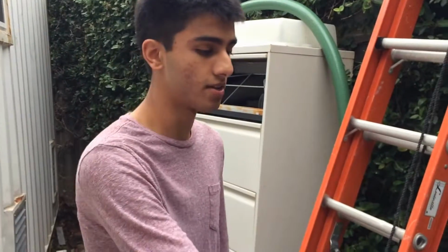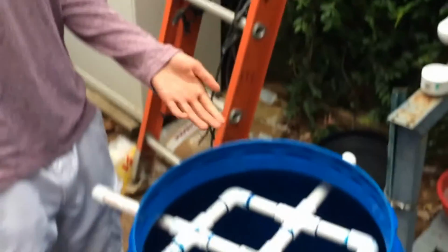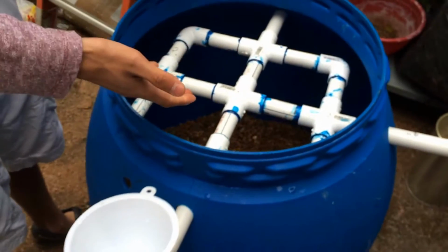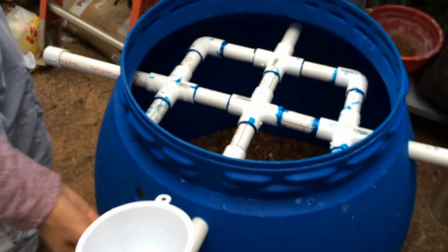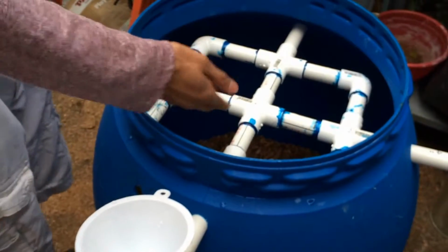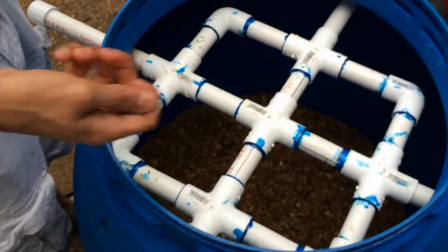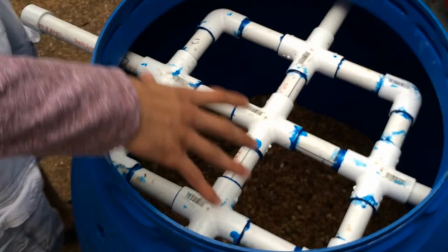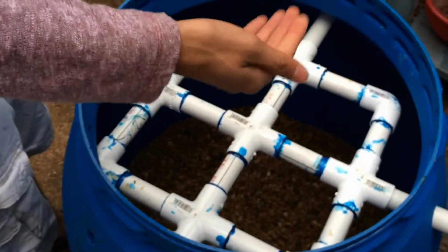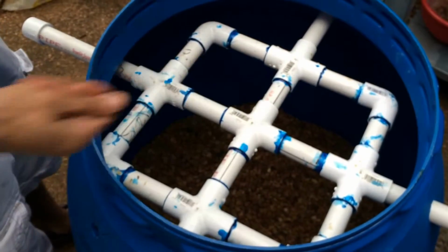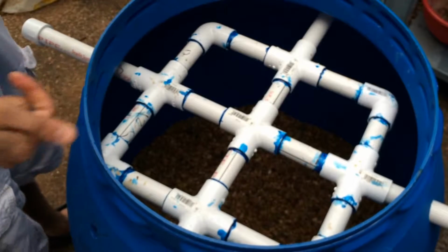After our water flows out of our anaerobic tank, it will then flow into the second stage of our treatment process, which is our aerobic tank. After flowing through our inlet pipe, it'll then flow to our trickling filter, which has small perforations along the bottom of our filter, which will allow the water to spread evenly throughout the gravel.